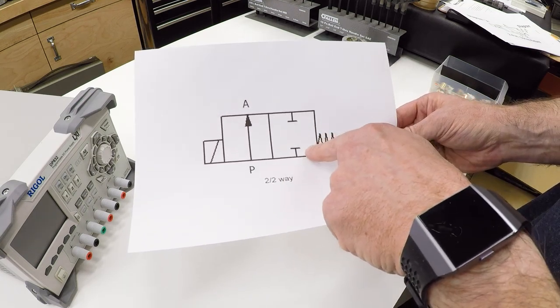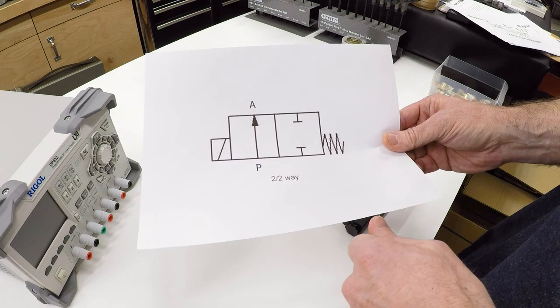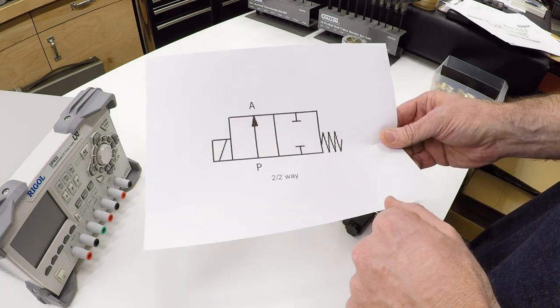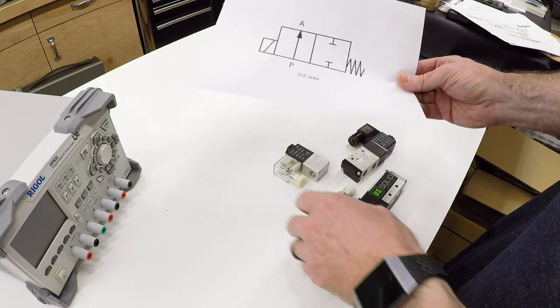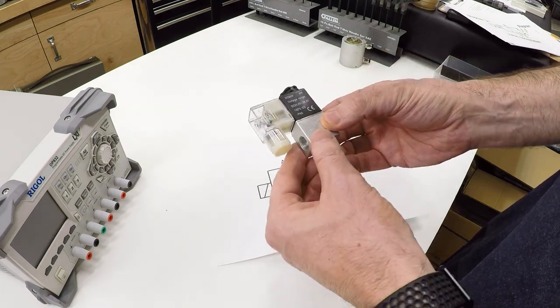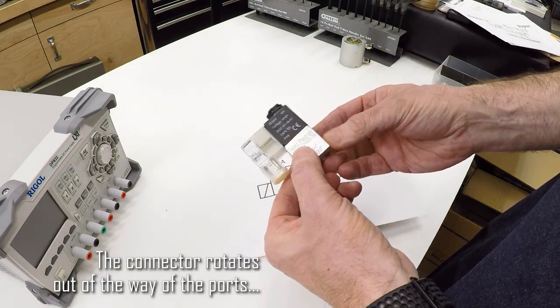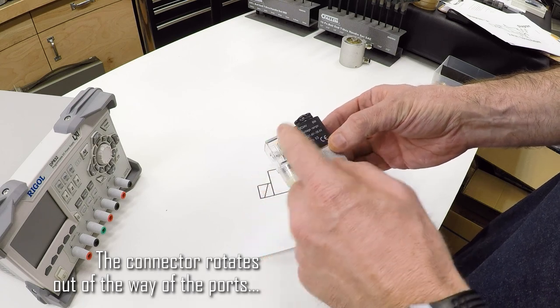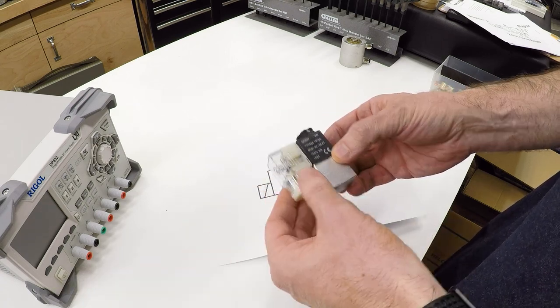When the solenoid is turned off, the spring returns the valve to this state where it's completely blocked. This is the simplest valve you're going to see. You connect your air inlet to the in port and the outlet to the out port, and when you turn on the current, the air flows. When you turn off the current, it stops.